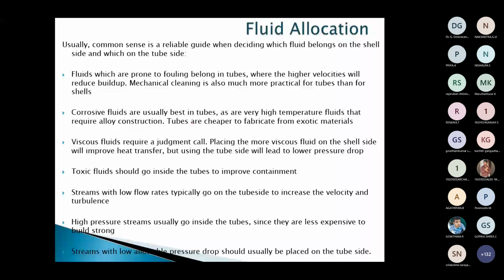If you consider the viscosity of the fluid, the selection should be based on our requirement. If you want more heat transfer, then we should have the viscous fluid on the shell side. If you want a lower pressure drop, then we can use the viscous fluid on the tube side. So this is based on our requirement, right?